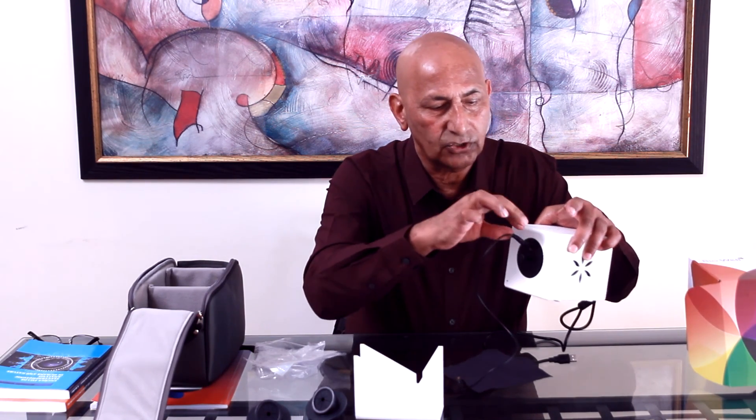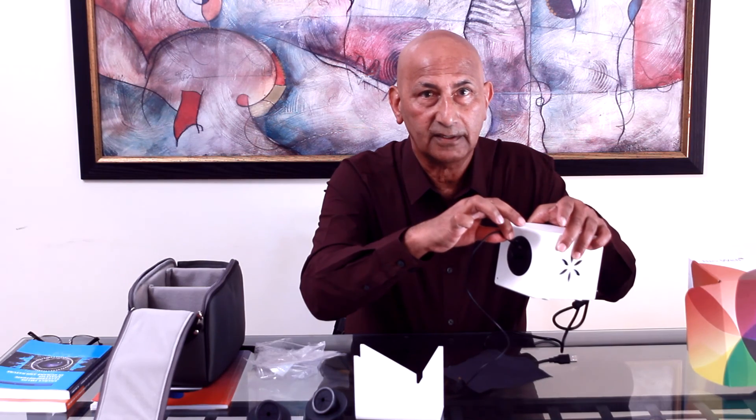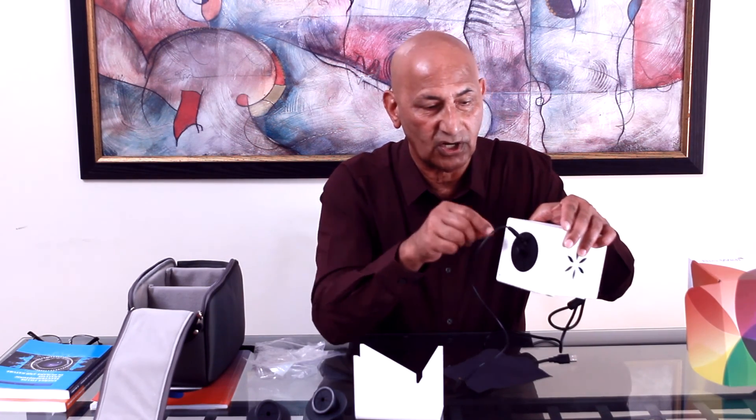The rule of thumb is do not pull the electrode wire while it is in the BioWell, because the consequences can be very, very adverse. The electrode will be pulled back, and when you release it, it will smash against the glass dielectric plate and crack it. At that point the two-year warranty on your BioWell is null and void because of carelessness — and we do not want carelessness.